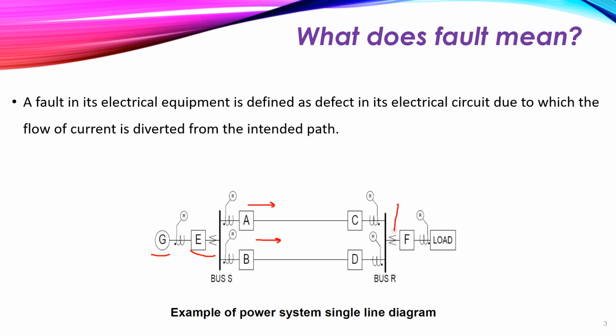Here, we also have a transformer, which is a step-down transformer to reduce the transmission voltage to a voltage suitable for our load. So the power comes from the generator here, goes through the transmission lines, then reaches the load. Okay, so this is the flow of the current, or the flow of the power, from the generator to the load. So here, this is the normal path, the intended path for the current itself. Now, assuming a fault occurred, for example, at the transmission line here. So what happens when a fault occurs?